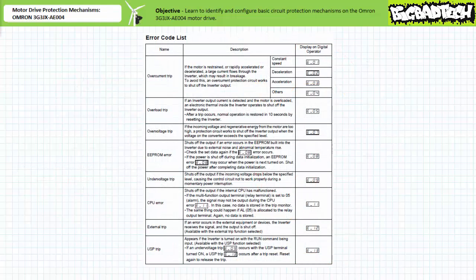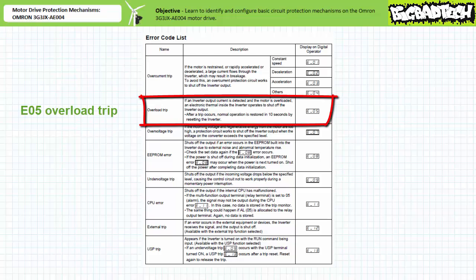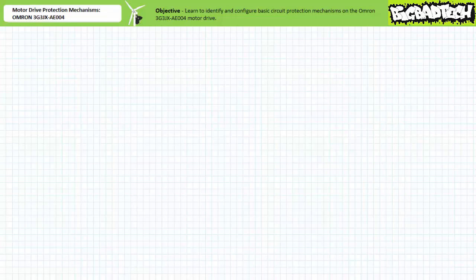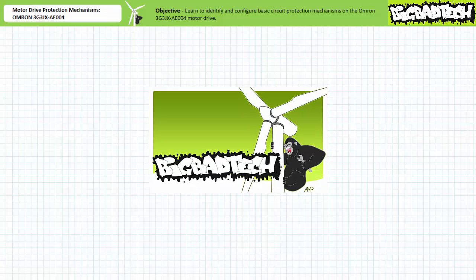One of the more important alarm events is E05, an overload trip. An overload event is a high current draw that, while temporarily permissible, may be damaging if it is sustained for any length of time. An example of an overload condition might be when a motor experiences unusually high torque or the rotor locks up. These periods of sustained high current draw might damage a motor's insulation and windings over time due to high heat. An overload is therefore a function of two quantities: current magnitude and time.